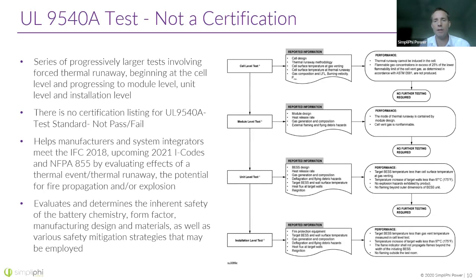We look at the heat release rate, the generation of gases, the potential for deflagration (explosion), and the possibility of flying debris in an explosion. We test to make sure surface temperatures don't get too hot on the battery or container walls, and check for the potential for reignition after a fire might have gone out.